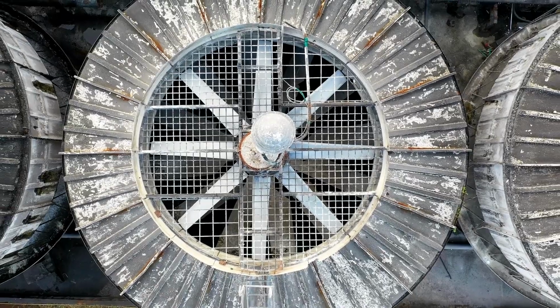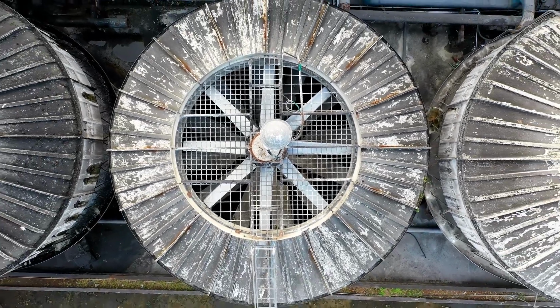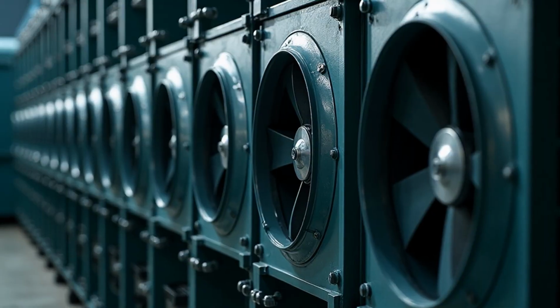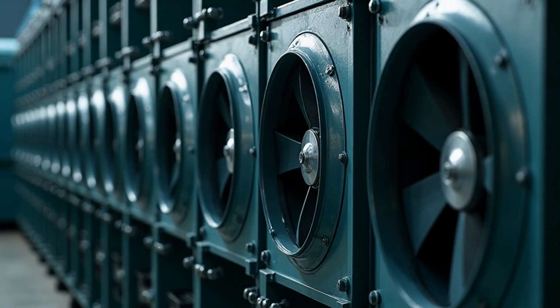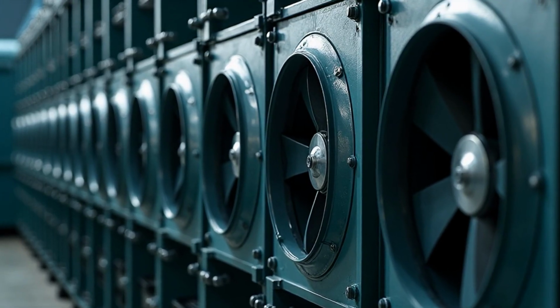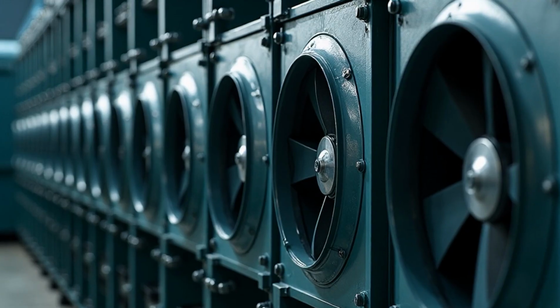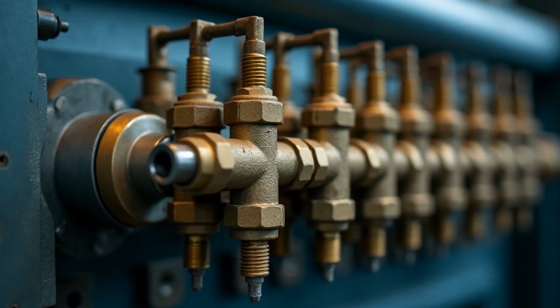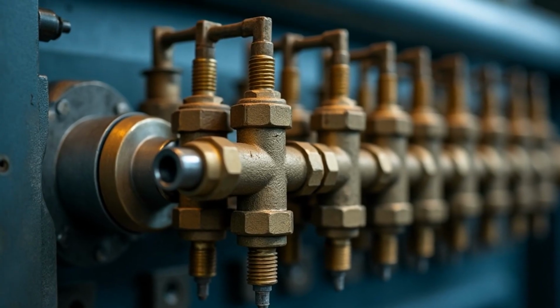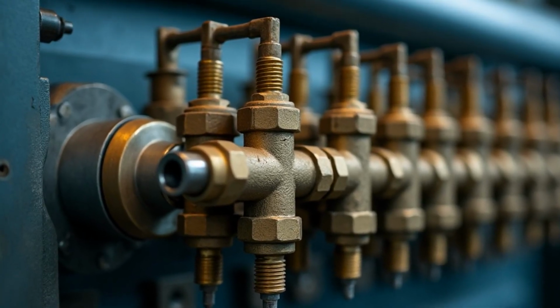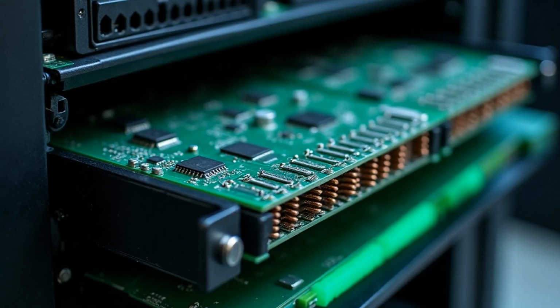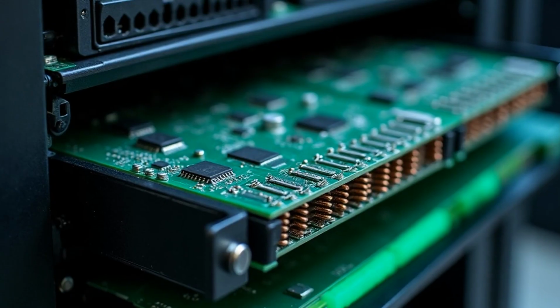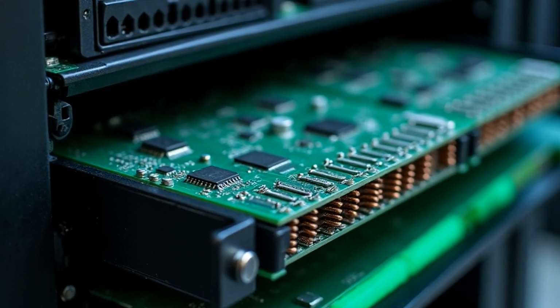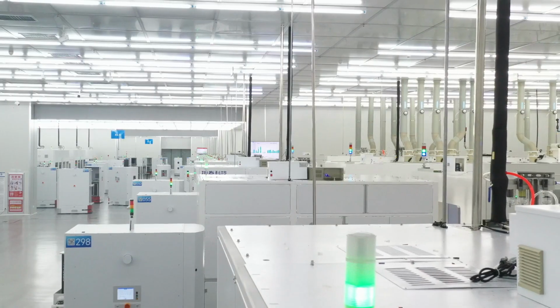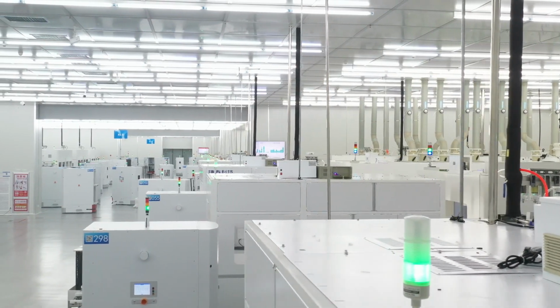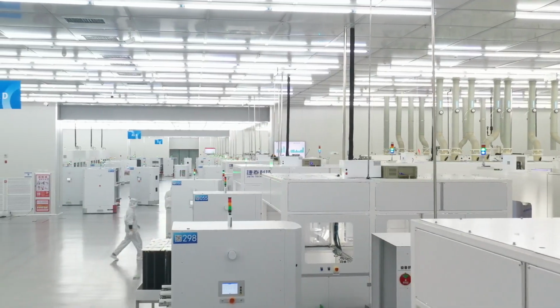At that point, a fan is not a weak solution. It is not a solution. Air carries very little heat for its volume. Moving a rack's worth takes enormous flow, and the faster you push it, the more the fans eat. The industry did not switch to liquid because liquid is fashionable. It switched because the next generation has no air-cooled version at all. No air variant at any power level. The compute trays and the switch trays ship without fans in them. Air did not get worse. The chips walked off the end of what air can do.